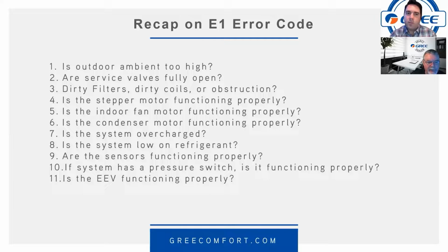we covered 11 different things here. Outdoor ambient too high. We've got charts out there for you. Are the service valves fully open? Easy thing to check. Dirty filters and coils, probably the most common thing. Again, easy visual check and should always be done. Is the stepper motor functioning properly? Indoor fan, condenser fan. Is the system overcharged or is it low on refrigerant? And then are the sensors functioning properly? If it has a pressure switch, is that functioning properly? Easy to check, not as easy to change. Is the EEV functioning properly?